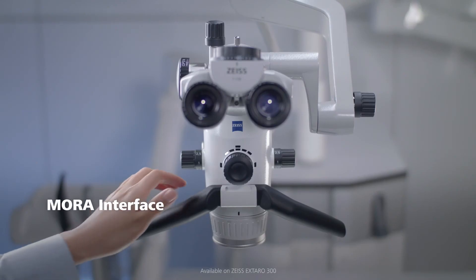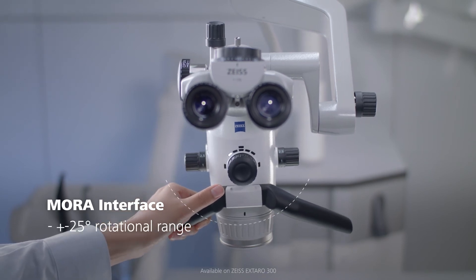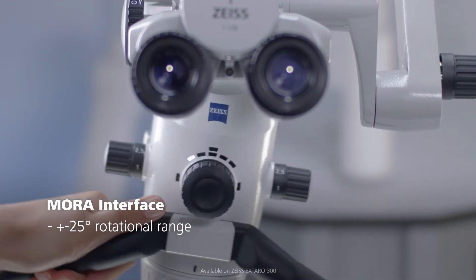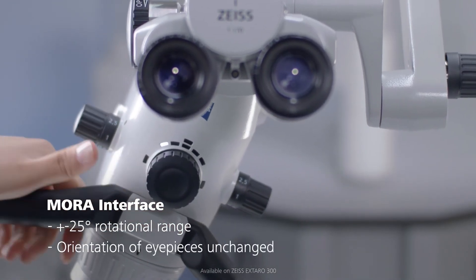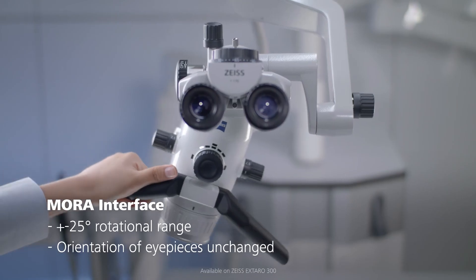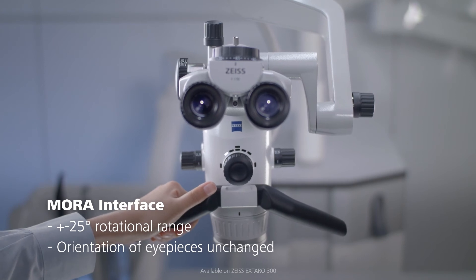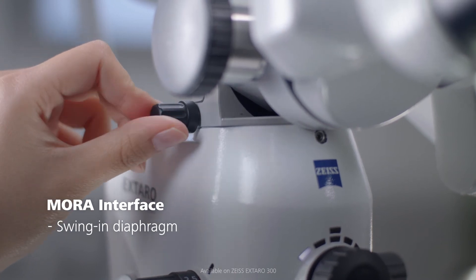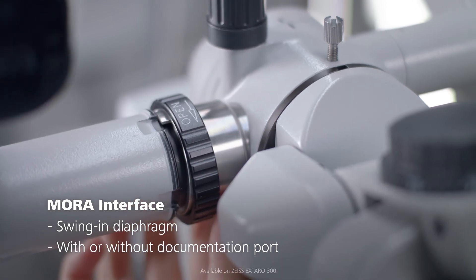The MORA interface offers a rotatable coupling system for the microscope body with plus minus 25 degrees rotational range, which enables you to change the angle of observation without changing the orientation of the eyepieces and therefore without requiring you to change your upright ergonomic sitting posture. It also offers an integrated swing-in diaphragm to increase the depth of field. It is available with or without documentation port.